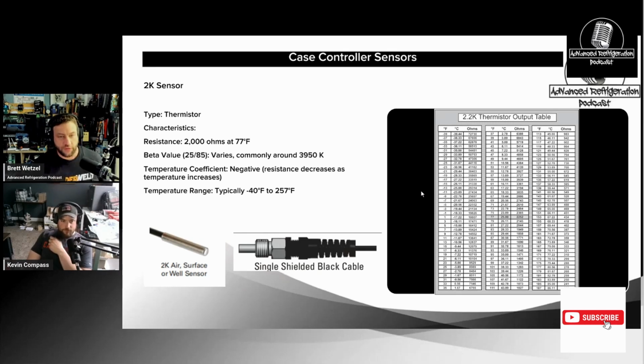And then you have the 2K sensors, which are big on the Sporlan superheat controllers, Sporlan subcooler controllers, K2 Novar, all the Novar stuff that goes to the 1081s and the 521s, the Minio boards. Funny thing is, a lot of times they do use them for the subcooler. So if you don't have a Novar sensor and can't find something, you can use a K2 Sporlan one.